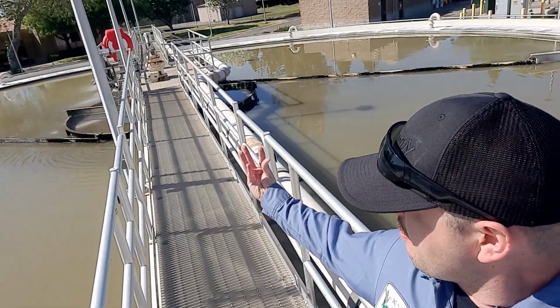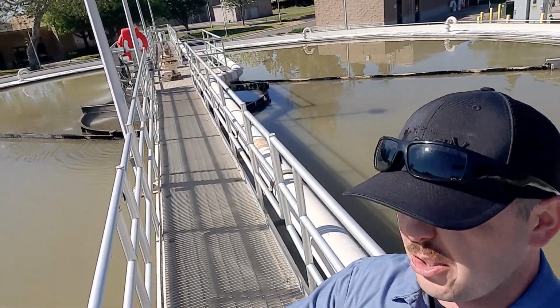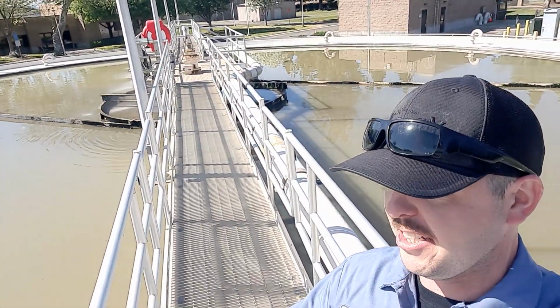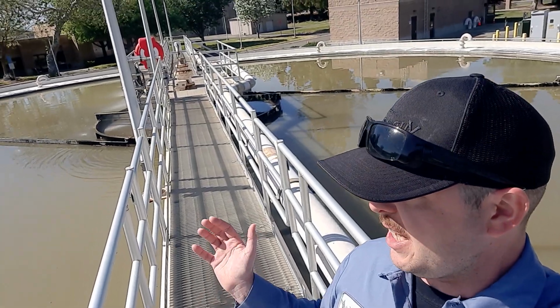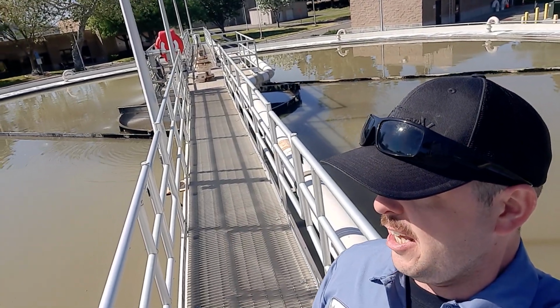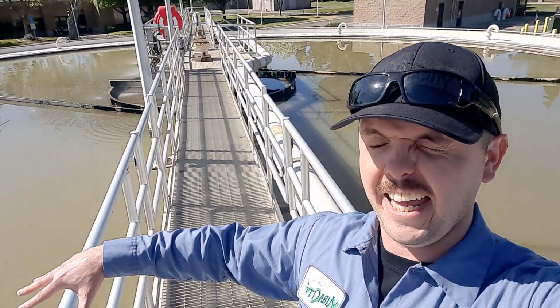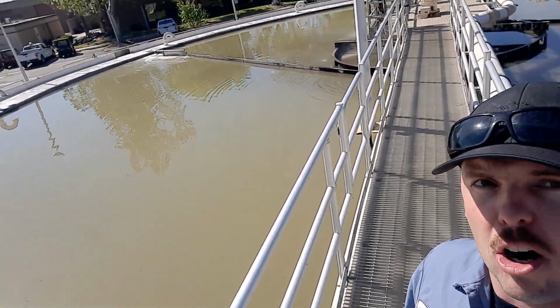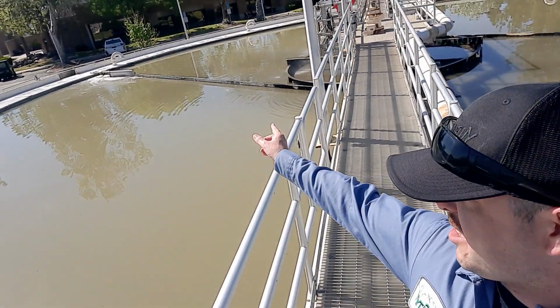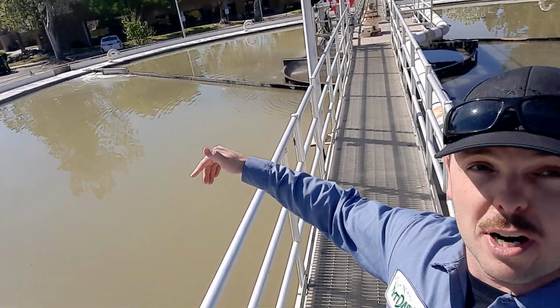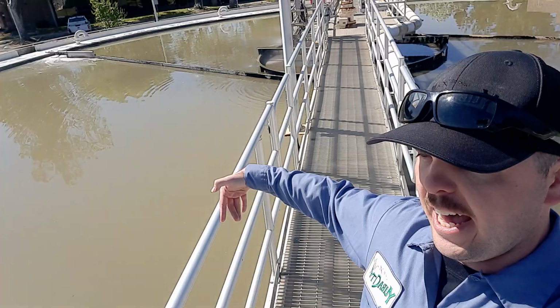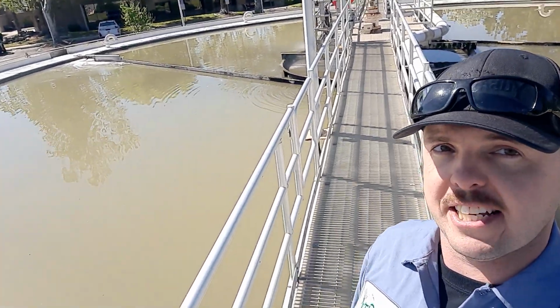It flows from the middle and moves to a larger surface area on the outside. The process of doing that slows it down. And basically by slowing it down, it allows the heavier sludges to settle to the bottom of this tank and all the scums to rise to the top. You can see that arm over there. There's one on the top grabbing the scum, one on the bottom pumping it to our digestion process.